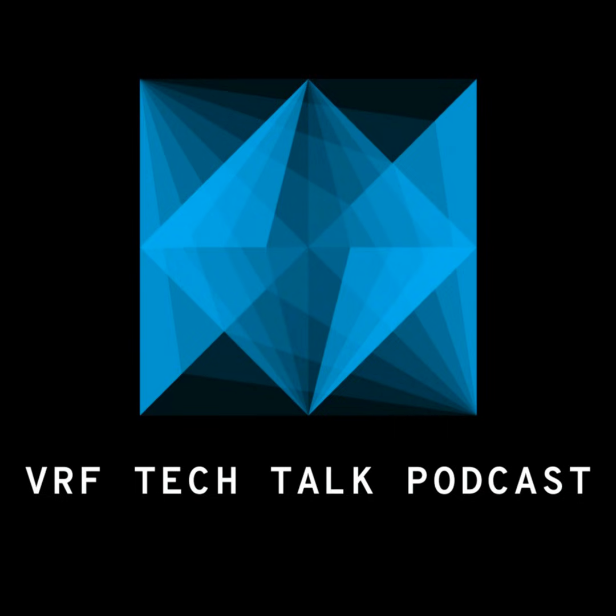But I would easily hang this one up on low charge, because if you prodded this and you didn't know and didn't go any deeper, let's just say you just looked at one of my videos on YouTube and you said, okay, 3 pillars, that's all Roman says to talk about. That's all I'm going to use. Screw everything else. You're going to say, okay, high discharge superheat, high suction superheat, high subcooling. Well, that points to a restriction, and it's like, what does it? You have those 3 numbers, but you can see, right, Donald, that you have to go deeper into it. Yeah. The valves are pinched off. If you had high subcooling and your valves were pinched off at your outdoor unit, then I would say you have a ton of subcooling, right?